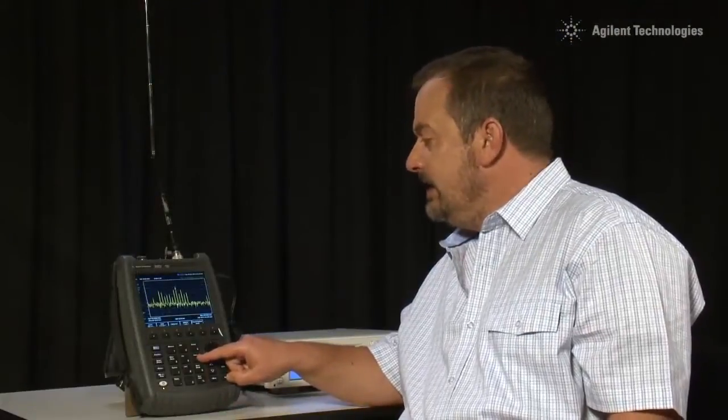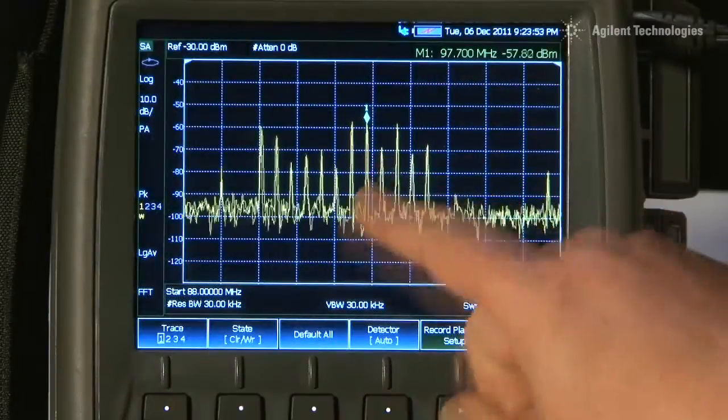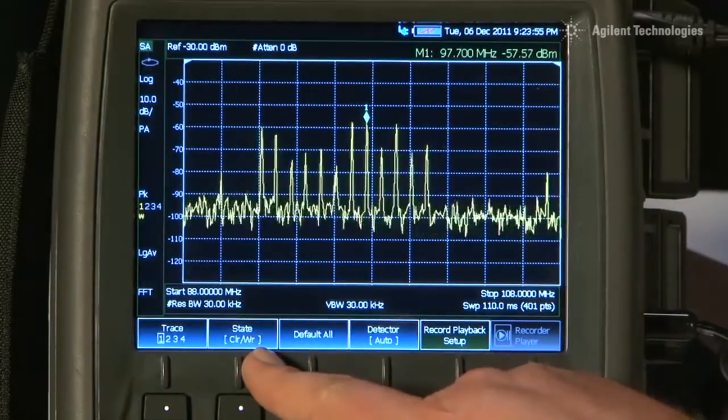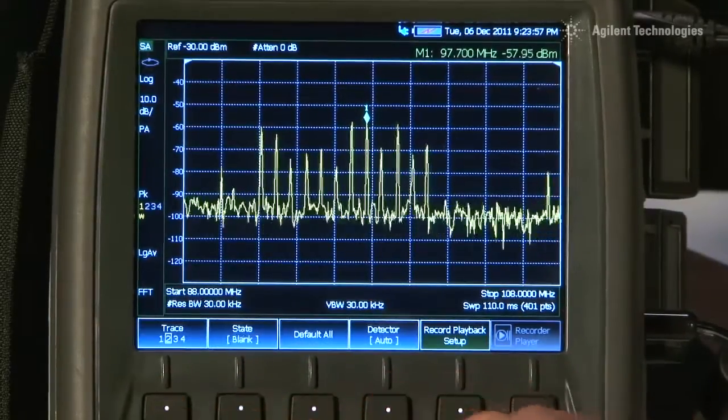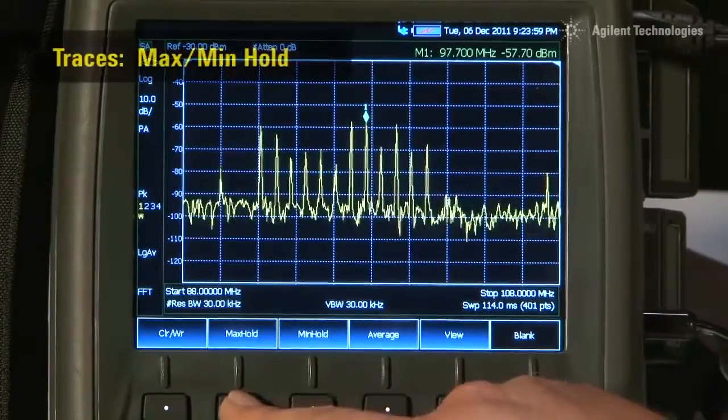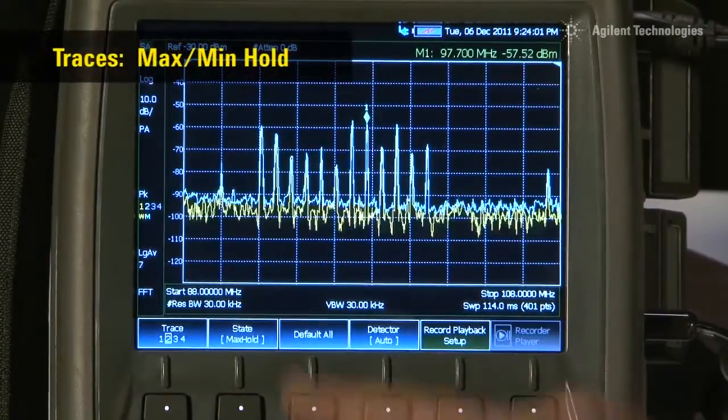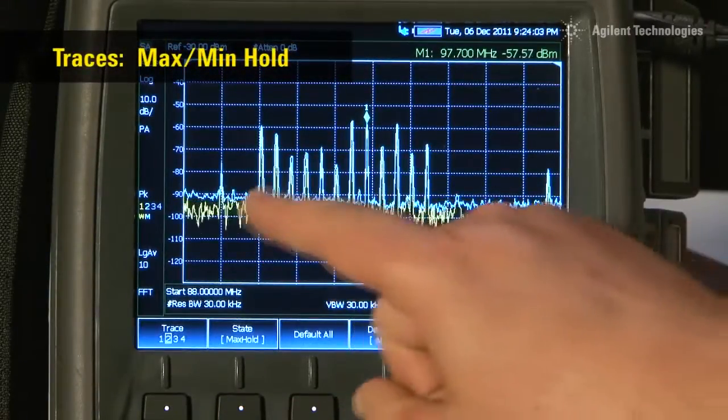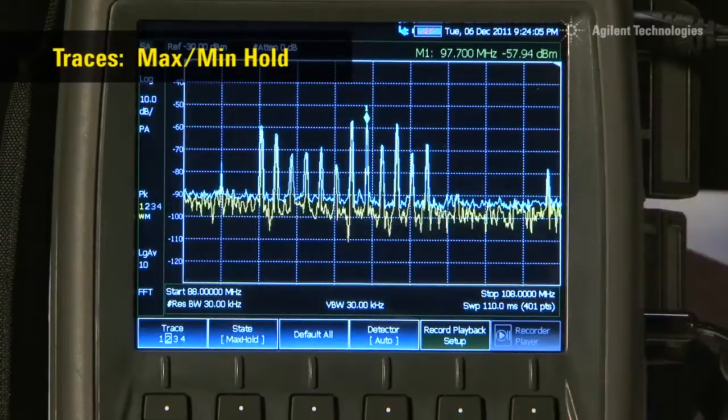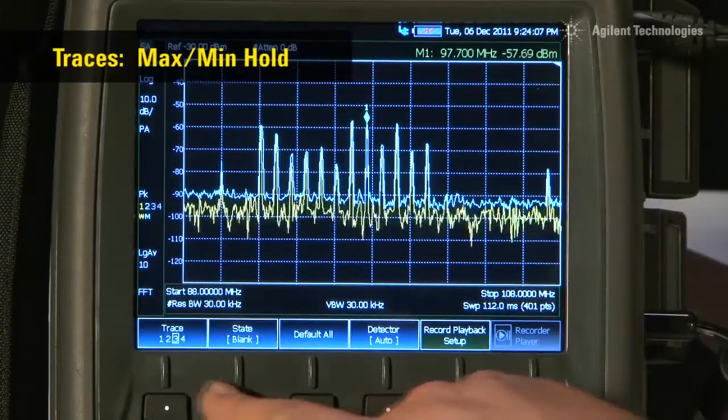If I press the trace button, you can see that trace 1 is here in yellow, performing a clear write operation. If I select trace 2, currently set to blank, but set it now to max hold, you will see in the blue or white trace it is storing the maximum value of the signal, and we have got two more traces. Let us turn on trace 3 and set that to min hold.